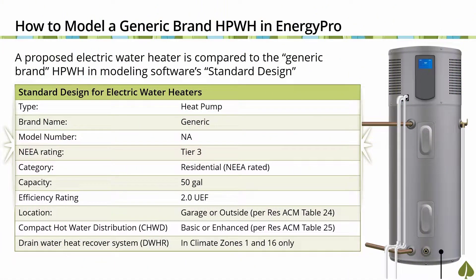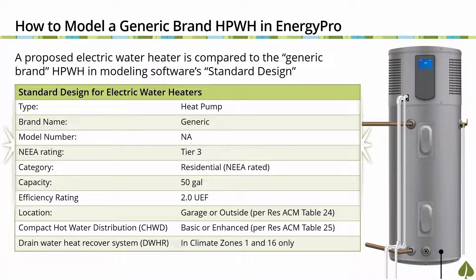When modeling low-rise residential buildings for compliance with the 2019 energy code, the standard design for domestic hot water or DHW system serving individual dwellings is based on the prescriptive requirement found in section 150.1 C8 and the proposed water heater type being either gas or electric. When the proposed design specifies an electric water heater, the compliance software sets the standard design to a generic brand heat pump water heater with a NEEA Tier 3 rating, a capacity of 50 gallons, a UEF rating of 2.0, with the unit located in either the garage or outdoors depending on the climate zone.